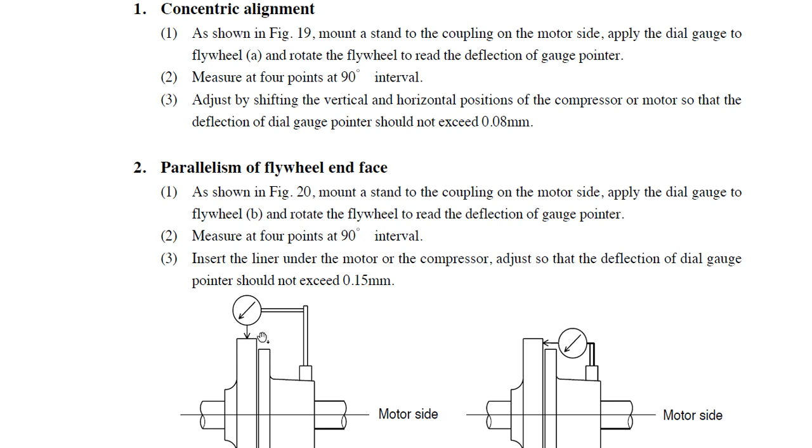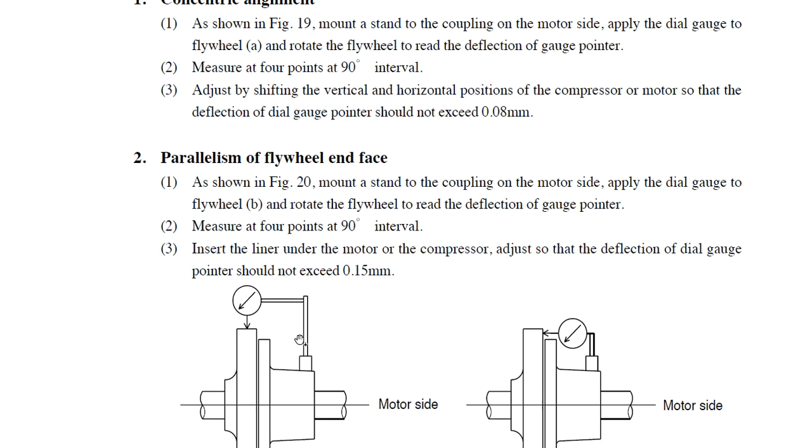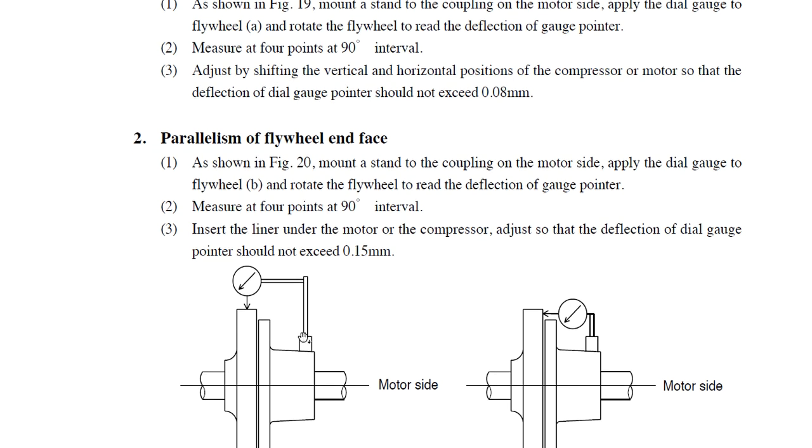As we rotate the flywheel, we will read the deflection gauge pointer. Measurements should be taken at four points with 90-degree intervals. Adjust by shifting the vertical and horizontal position of the compressor or motor so that the deflection of the dial gauge pointer should not exceed 0.08 millimeters.